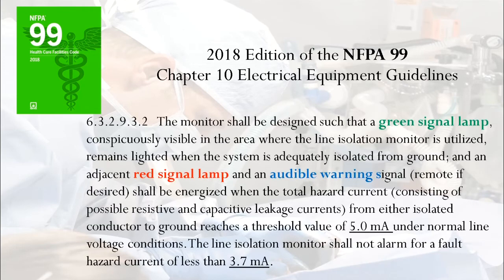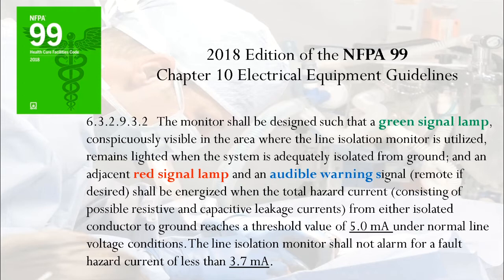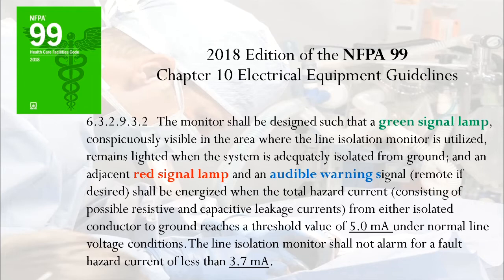In the NFPA 99 codebook, Section 6.3.2.9.3.2, talking about line isolation monitors: the monitor shall be designed such that a green signal lamp, conspicuously visible in the area where the line isolation monitor is utilized, remains lighted when the system is adequately isolated from ground, and an adjacent red signal lamp and an audible warning signal, remote if desired, shall be energized when the total hazard current — consisting of possible resistive and capacitive leakage currents from either isolated conductor to ground — reaches a threshold value of 5.0 milliamps under normal line voltage conditions. The line isolation monitor shall not alarm for a fault hazard current of less than 3.7 milliamps.